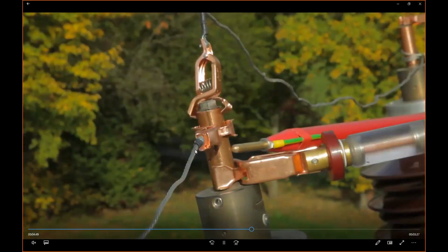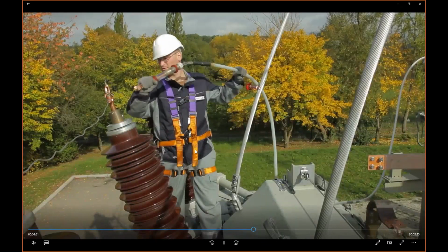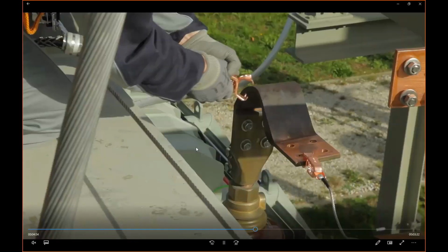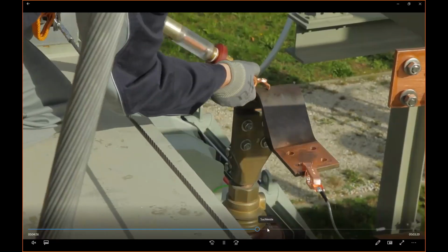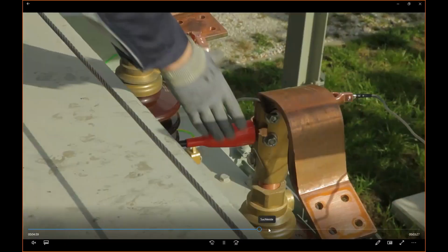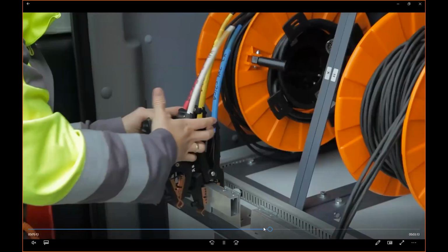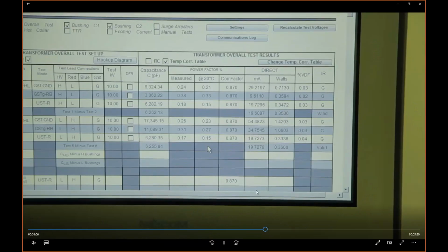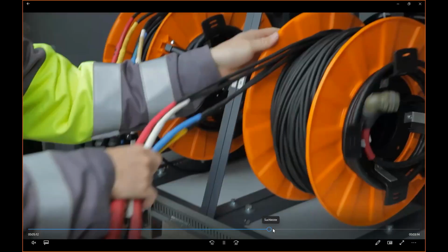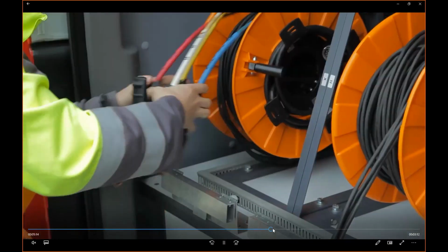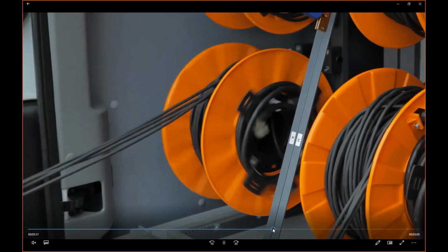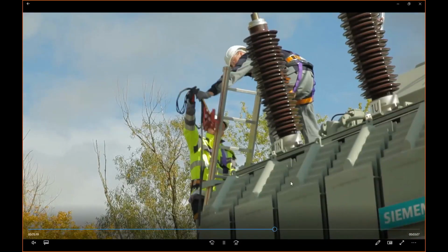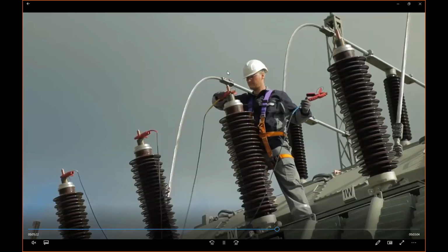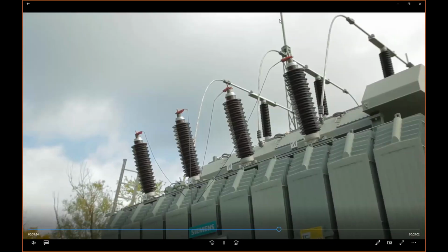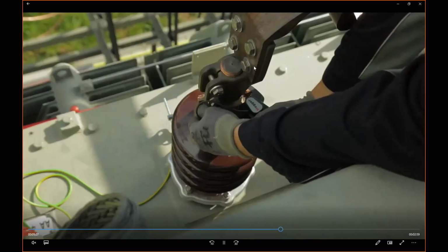And if you are reconnecting the leads, again, you are swapping the leads and making the second half of the report completed. So after you've done HV tests, all your tables are done for insulation resistance and for tan delta. Imagine you have also done the bushing tests. You are continuing with LV. And here you remove the short and you connect each phase now individually with the Kelvin lead on the HV and LV side.